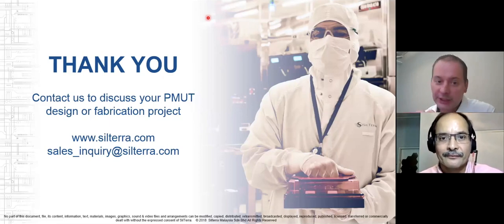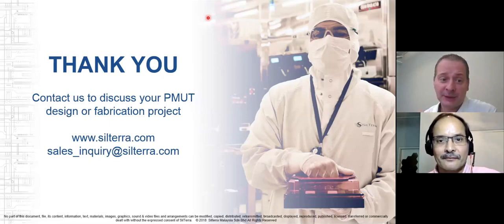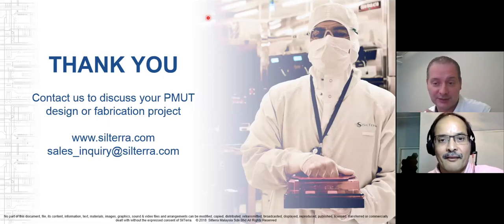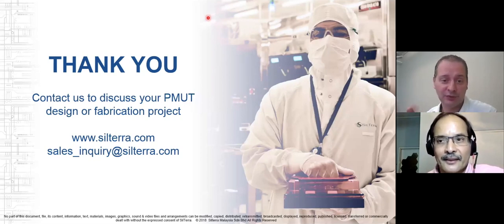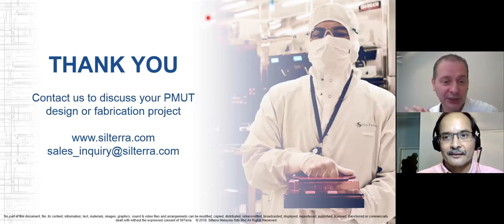Another specific question: what is PMUT cavity depth and frequency? Well, I can't reveal the depth as such, but frequency, as I mentioned, we have the ability to create all the way from 200 kilohertz to 30, 40 megahertz. I showed that on the slide. That was a great slide, with the frequencies and the applications.